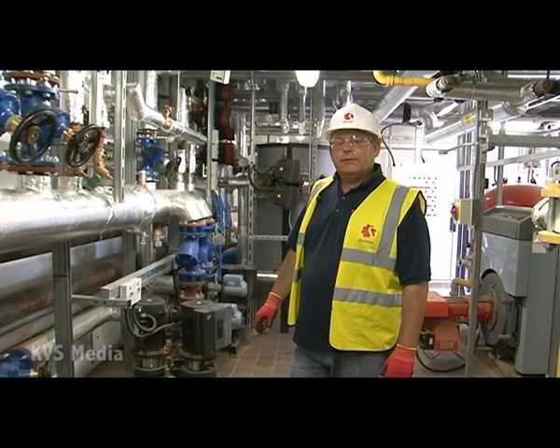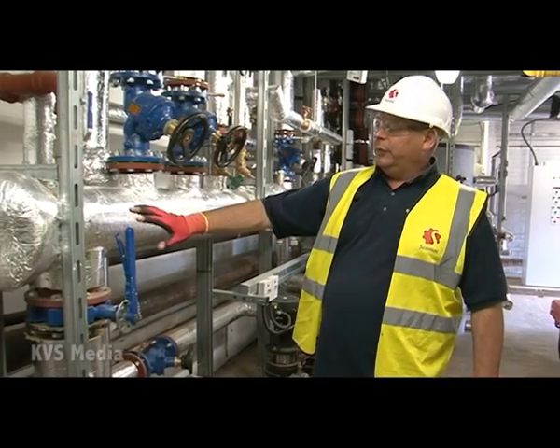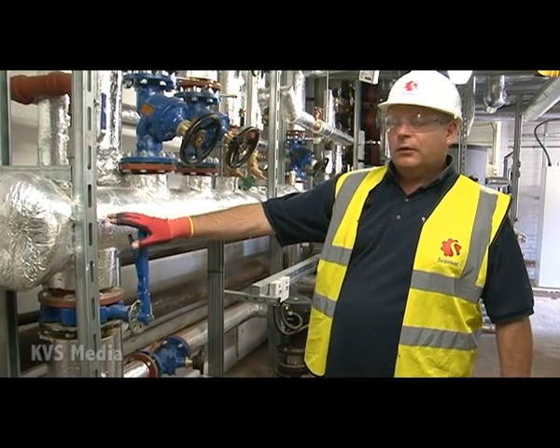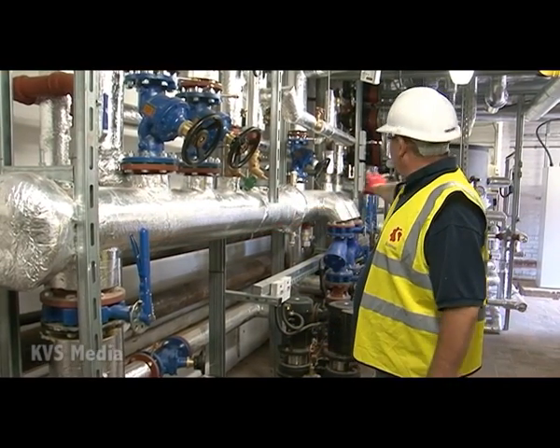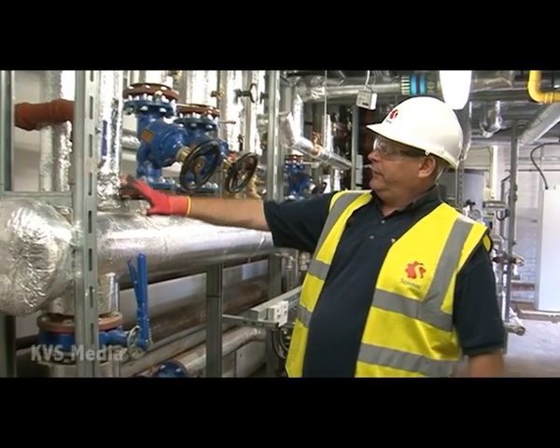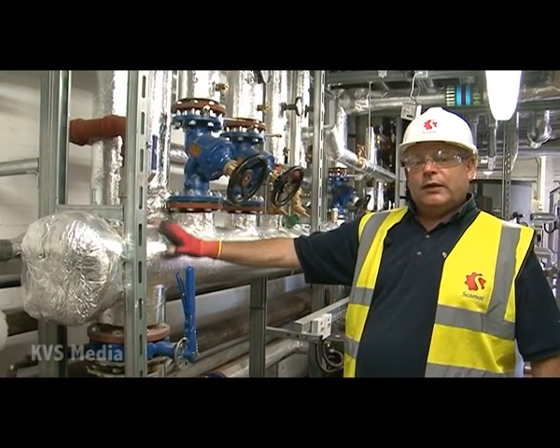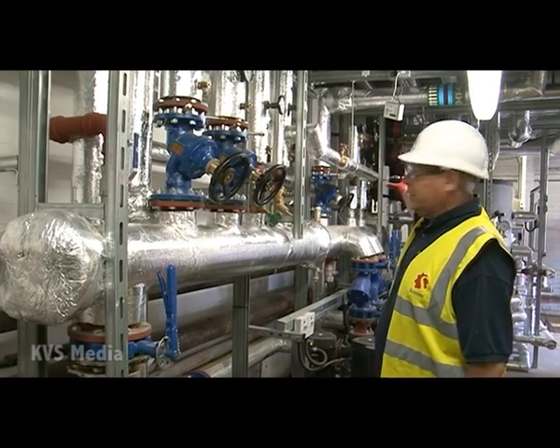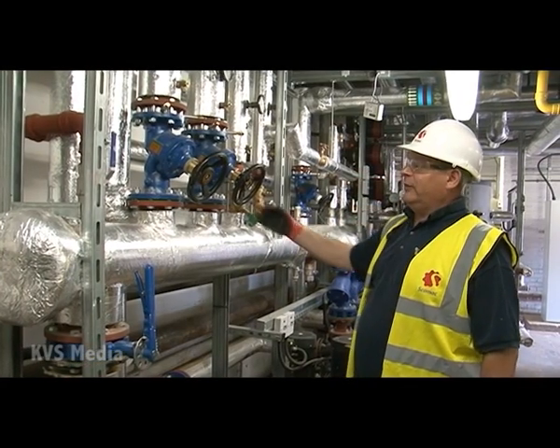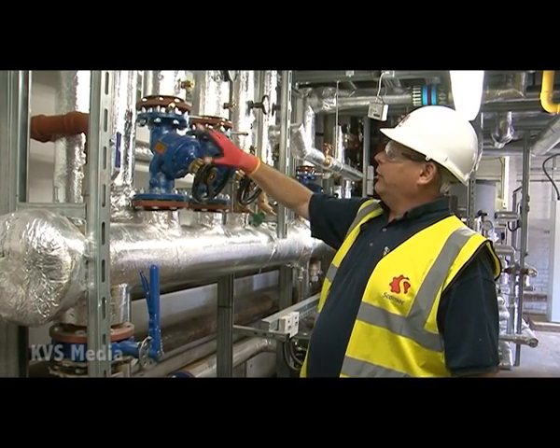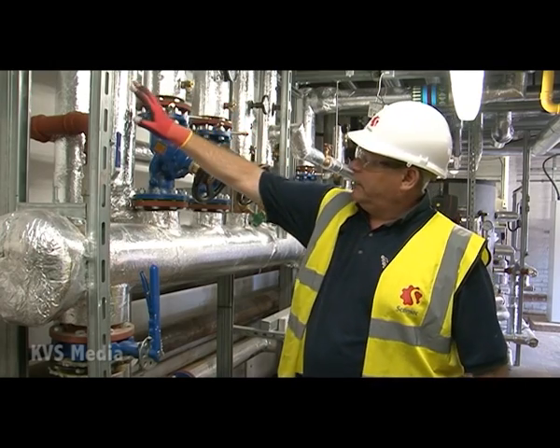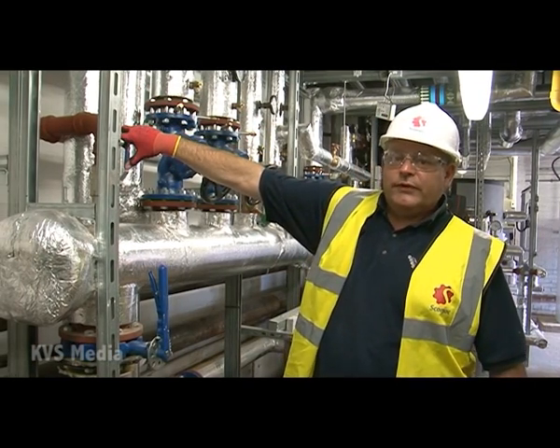We're now in the main plant room. Basically this was the existing plant room, and what we've done is we've altered the pipework to form what's called a low loss header, which is this big long pipe here. Basically we have all the returns for the building on one end and all the flows for the building come back in on the other end and mix in the middle. So I'll go through the valves. The first valve on it is the hot water return.